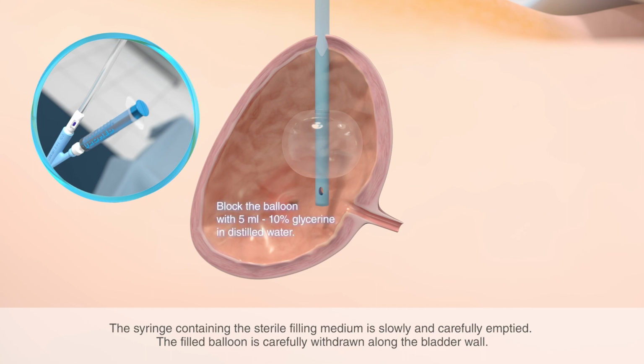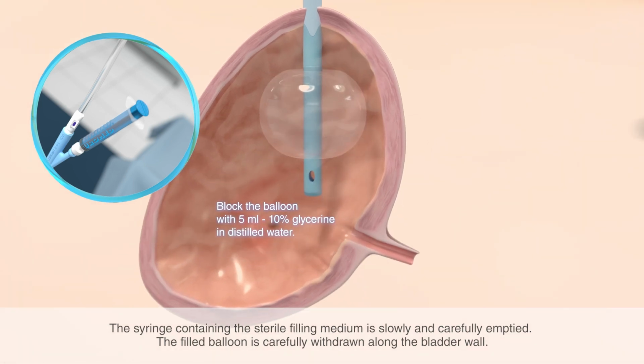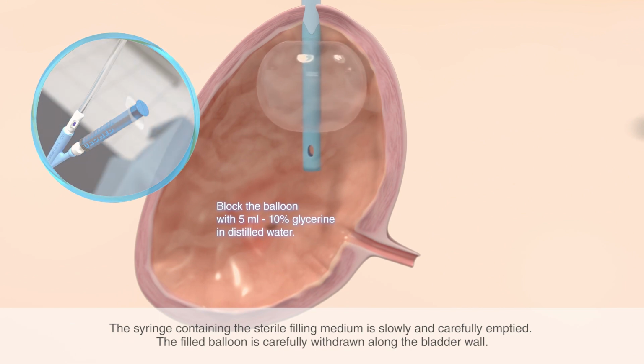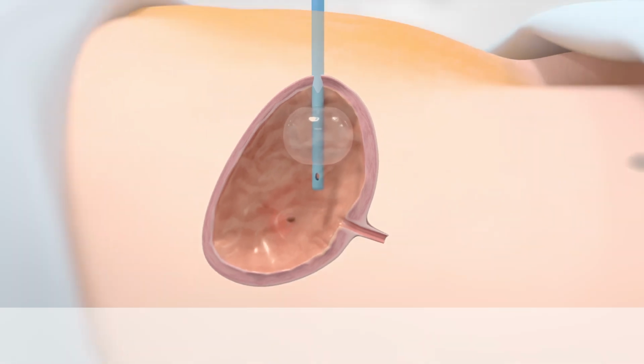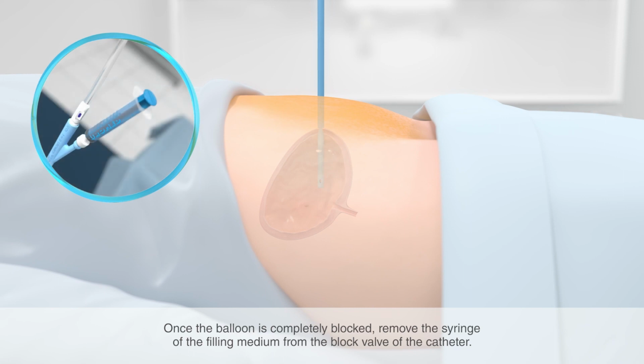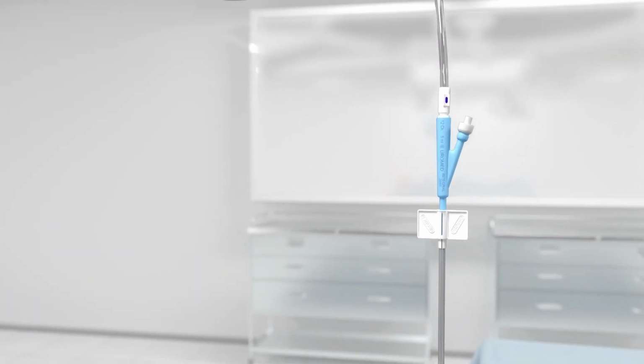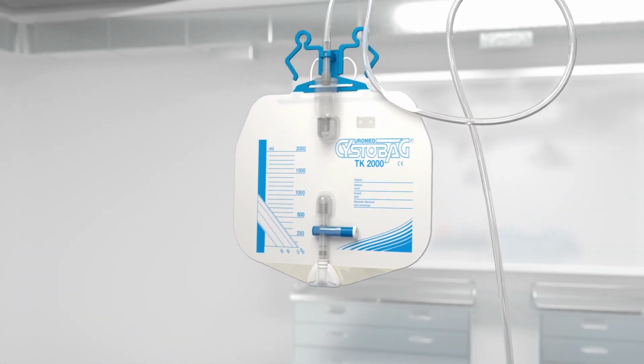The filling medium contains a 10% glycerine in distilled water solution. This helps to reduce diffusion of the filling medium out of the balloon and to keep the filling medium stable. Remove the filling medium from the block valve of the catheter as soon as the balloon is blocked. The urine is drained using the connected urine drainage system.